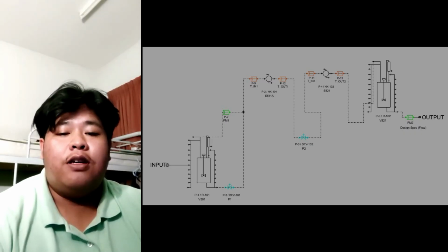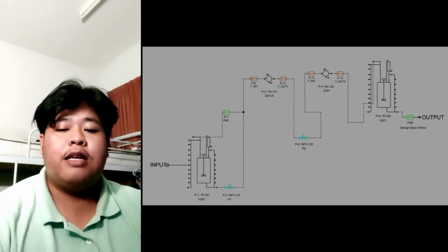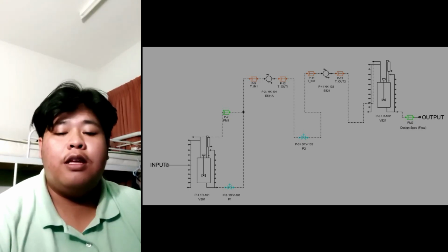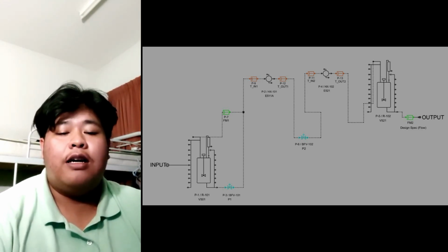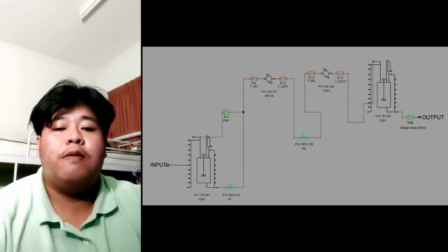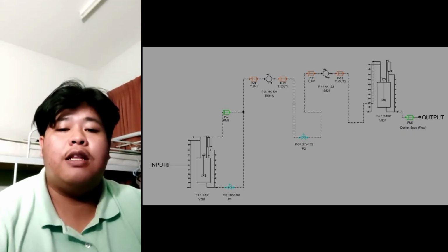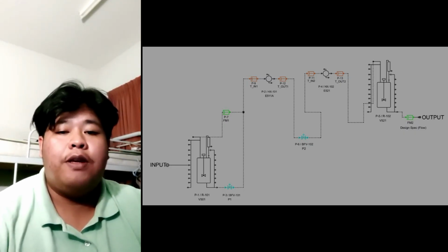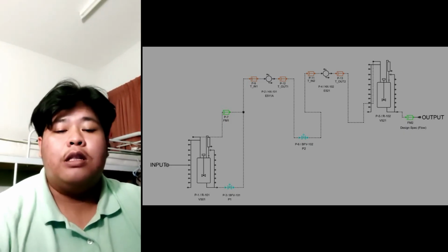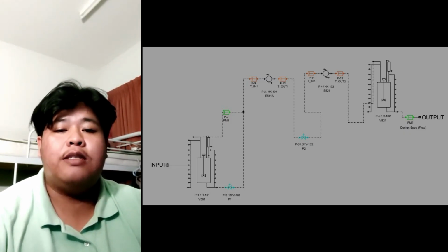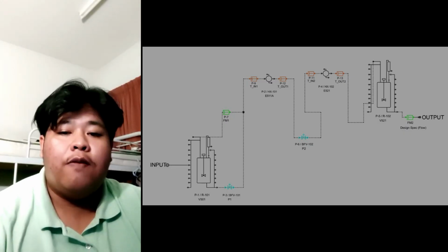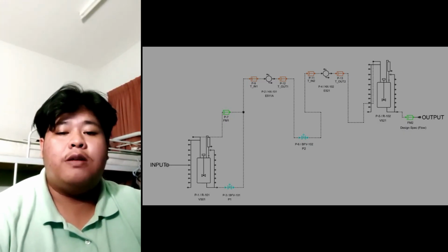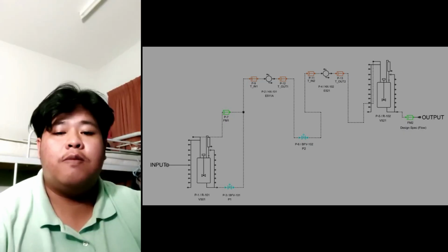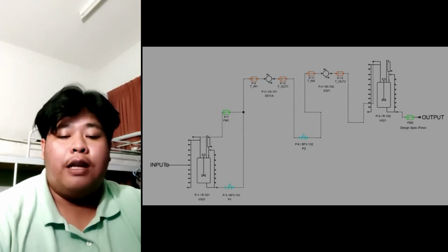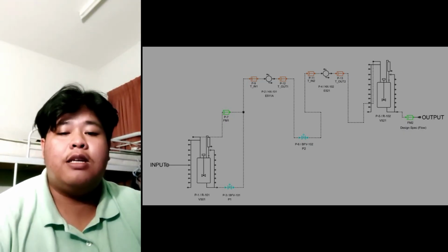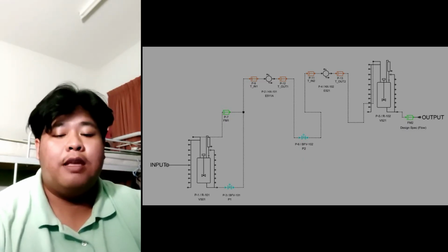The PID controller continuously reads the data from the sensor. For example, if T_OUT1 reads a temperature that is too high, the PID controller calculates the error and immediately sends signals to the upstream valve, BFV-101. The valve opens or closes slightly to adjust the flow rate measured by the flow meter FM1, bringing the temperature back to the set point. This ensures the process conditions at the E511A and the subsequent exchanger E521 remain perfectly stable.